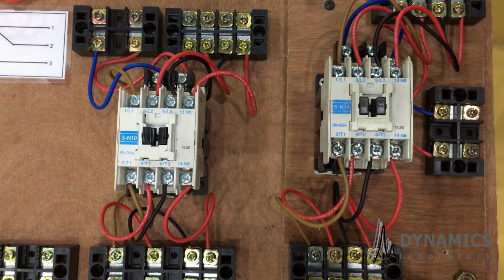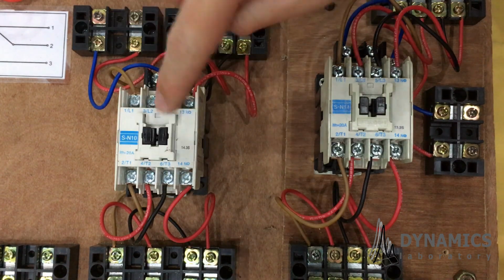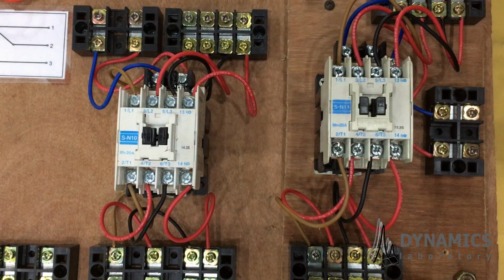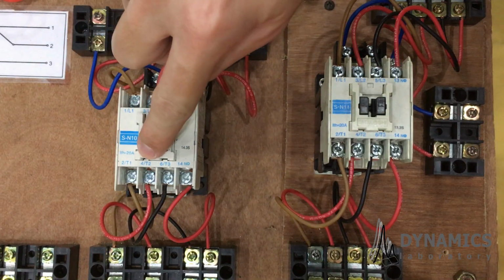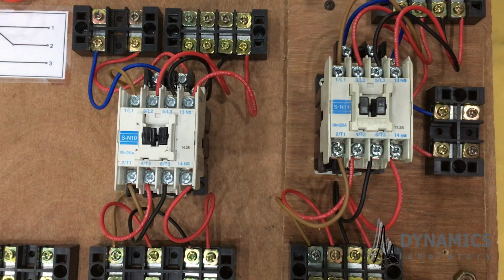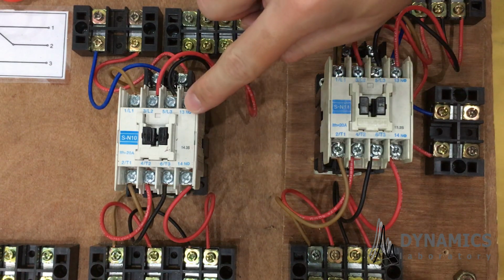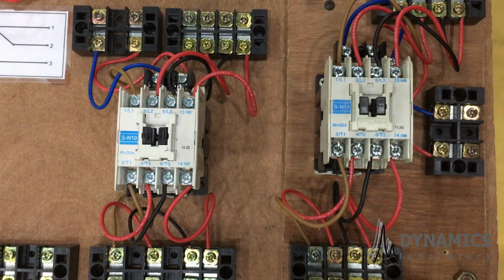Contactor. The contactor consists of 4 switches and a coil. 3 switches are for the high current circuit or load, and 1 switch is for the low current circuit or control. Take a look over here. You can see terminal 1, terminal 2, terminal 3, terminal 4, terminal 5, and terminal 6. These terminals are used for the high current circuit or load. Meanwhile, terminals 13 and 14 are used for the low current circuit or control.